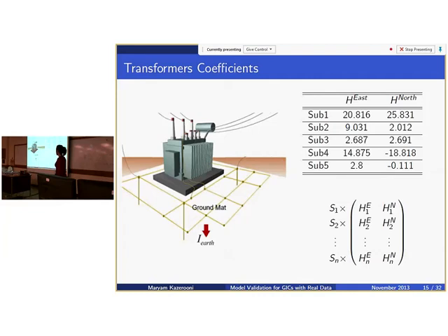And the only reason we're only considering this kind of inaccuracy is that we know that it exists. Like, we know that the grounding resistance is for sure not accurately available. So it's unknown? Yeah, they are unknown, but you can use real data measurements to estimate them. Because it's the ratio of the actual grounding resistance, and we don't know what the actual one is, so there's no way we can calculate it.